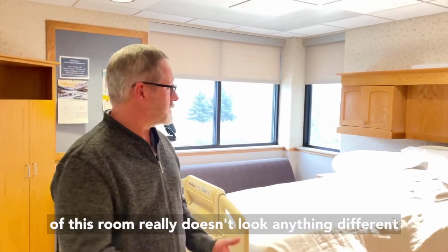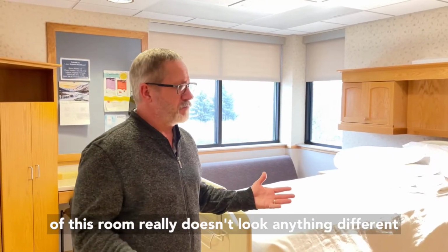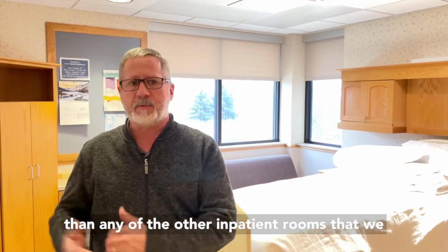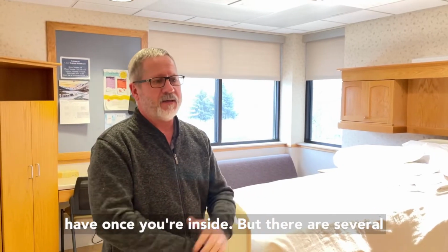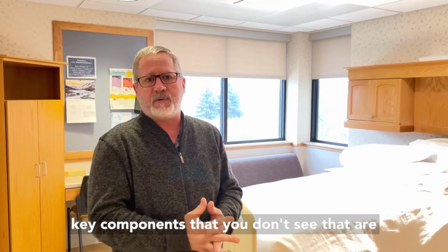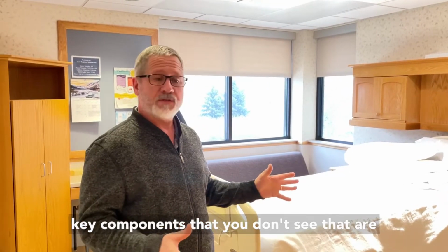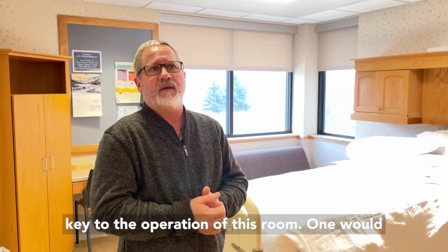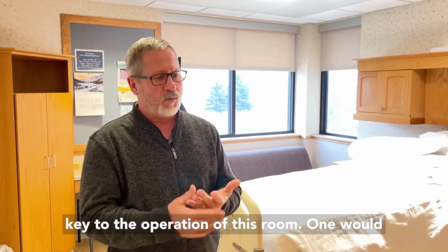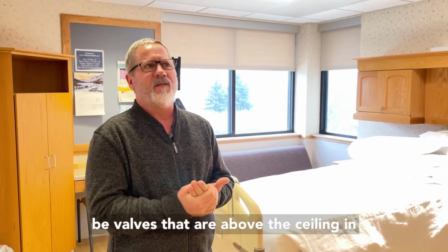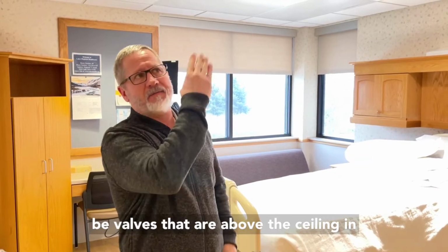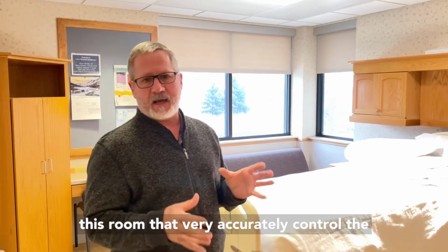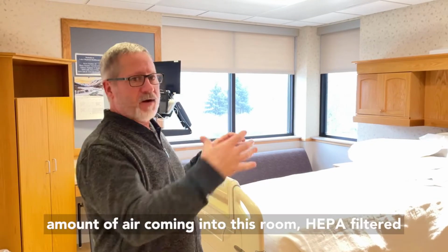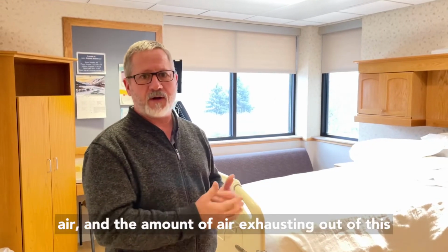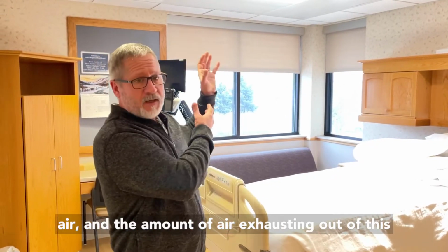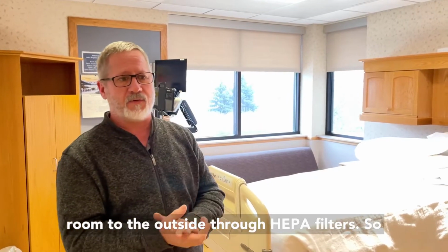Okay, so the inside of this room really doesn't look anything different than any of the other inpatient rooms that we have once you're inside. But there are several key components that you don't see that are key to the operation of this room. One would be valves that are above the ceiling in this room that very accurately control the amount of air coming into this room, HEPA filtered air, and the amount of air exhausting out of this room to the outside through HEPA filters.